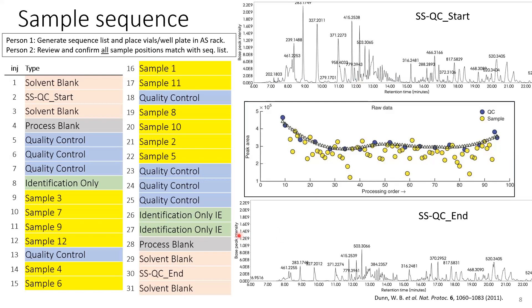Any questions about QC? What platform did you run this on? Is the drift translatable to different platforms? This figure is from a referenced paper, and the chromatograms are from a nano LC system piped to an Orbitrap in our lab. We typically see that you have a very good signal in the beginning, and then it goes down in performance across maybe 50 injections. This is a typical effect across different platforms. You may need to change your strategy — maybe more sample cleanup, or even diluting your samples and using less material.